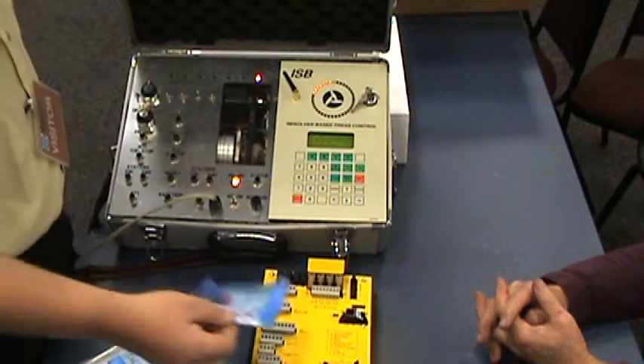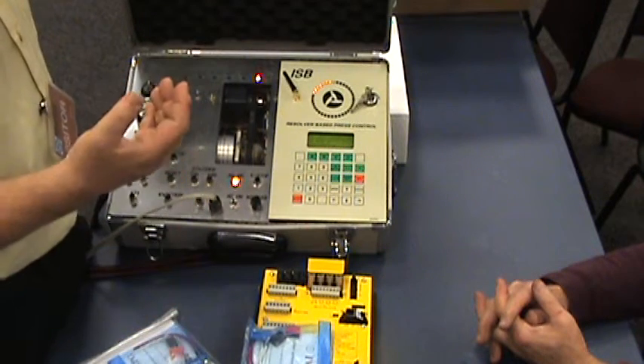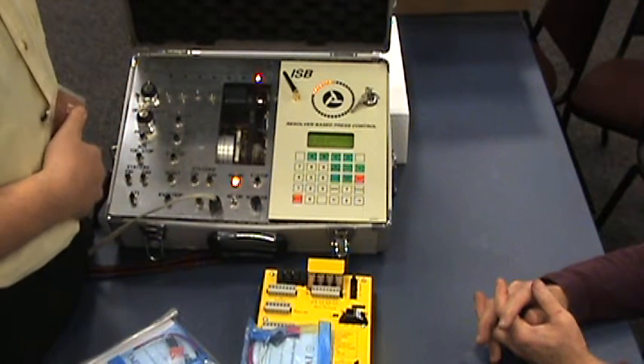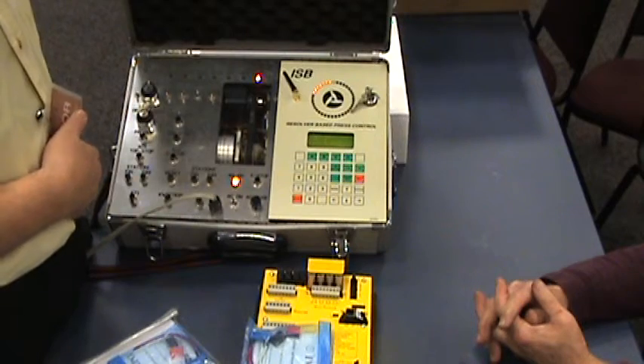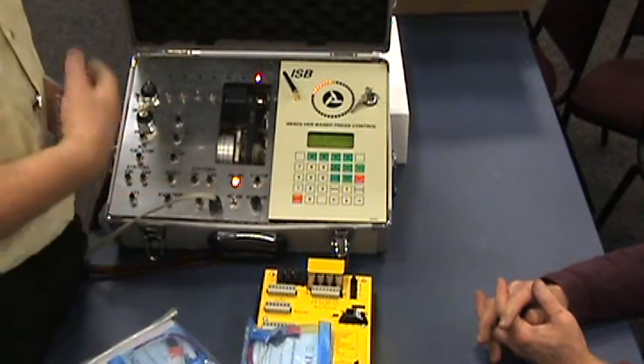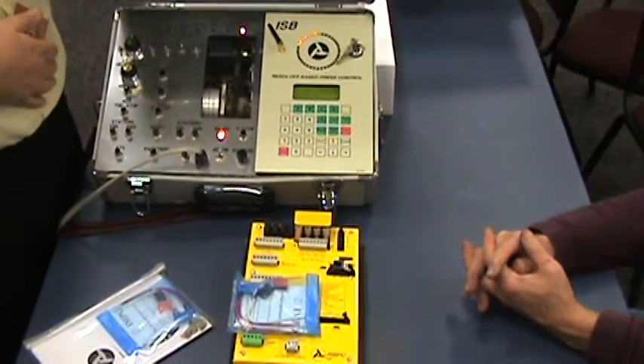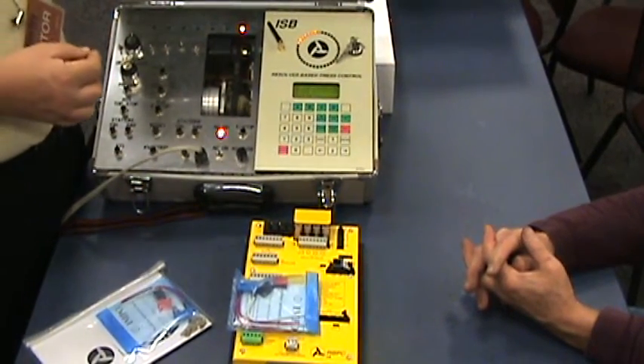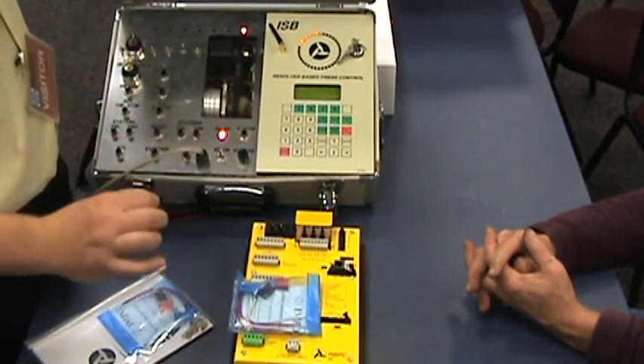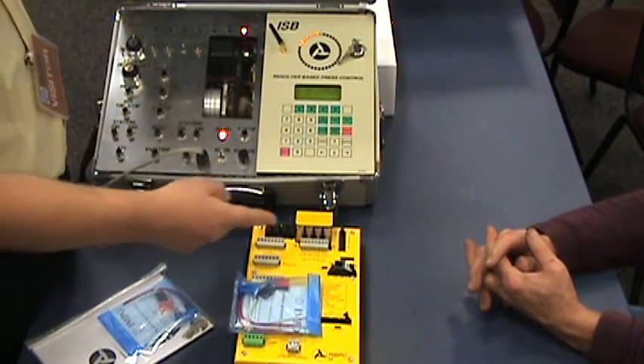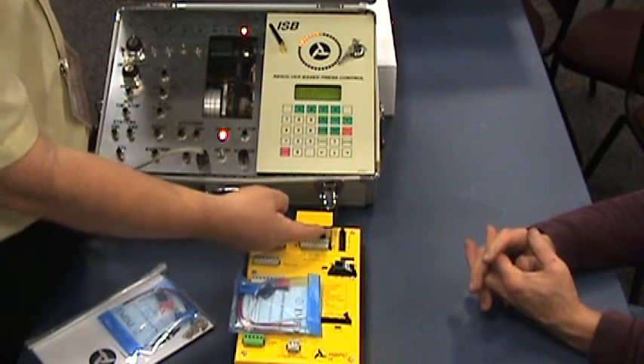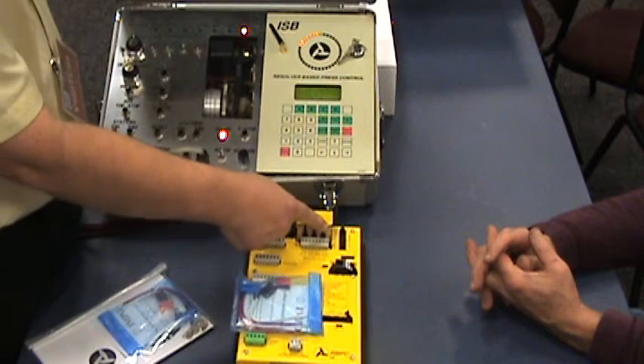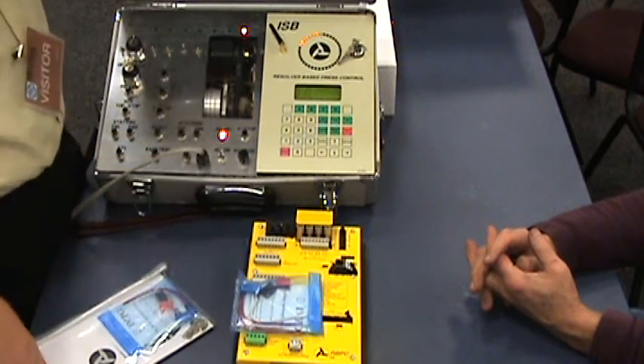It will do two things. The first thing is it suppresses the electrical surges that are created by a solenoid valve. So that's a good thing. It makes your electronics not get zapped over and over and over again by spikes. The second thing it does, which is even more significant from a maintenance point of view, is it extends the life of the relay contacts that are turning on and off that solenoid valve.